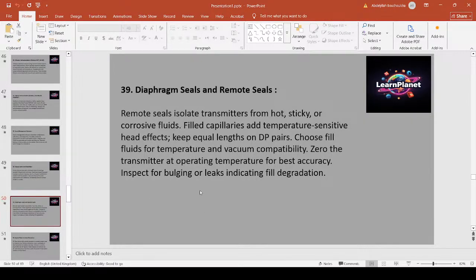Diaphragm seals and remote seals. Remote seals isolate the transmitter from hot, sticky, or corrosive fluids. Filled capillaries add temperature-sensitive head effects. Keep equal lengths on DP pairs. Choose fill fluids for temperature and vacuum compatibility. Zero the transmitter at operating temperature for best accuracy. Inspect for bulging or leaks indicating fill degradation.